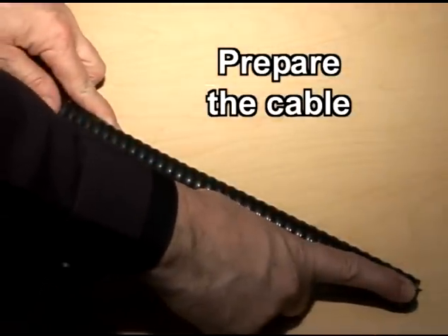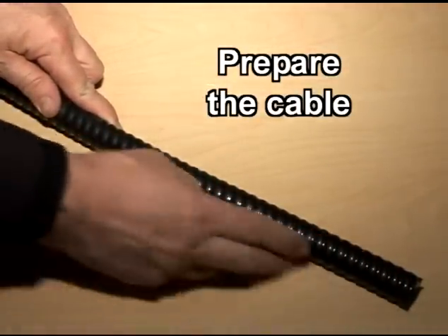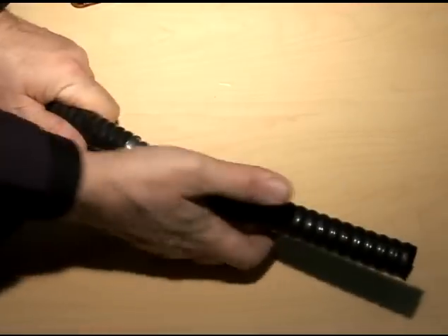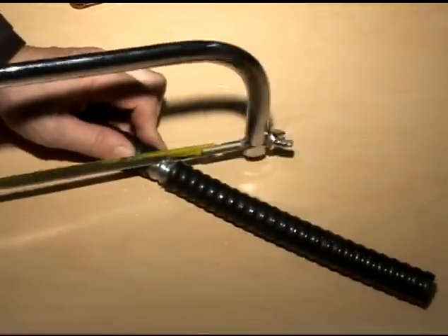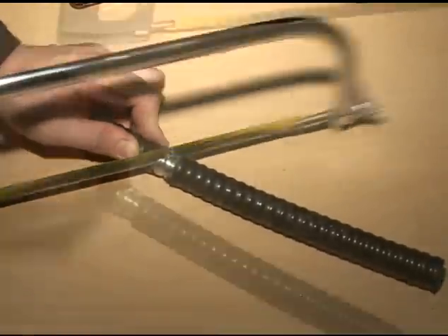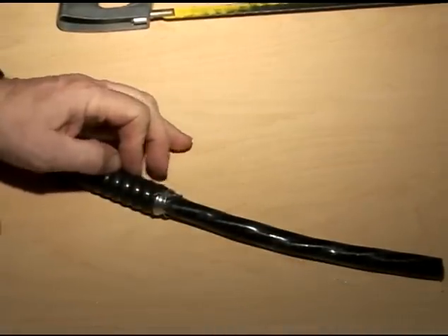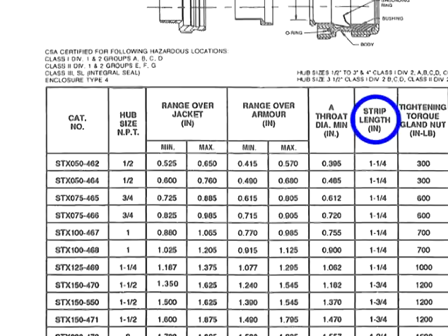The first thing to do is to prepare the cable. Begin by determining the strip length of the cable, then cut the outer jacket in order to expose one inch of the metallic armor, which we then cut using a saw at a 45-degree angle. We can now simultaneously remove the cable's outer jacket and armor. Use either the Star Teck XP instruction sheet or the wraparound ruler to determine the final strip length of the outer jacket.